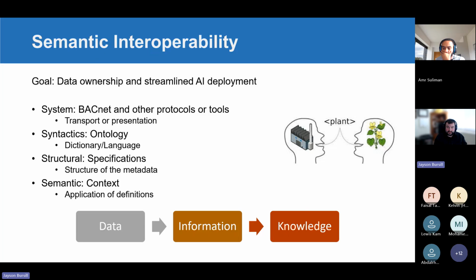Now, once you get there and you have all your data in one place, ontology becomes a thing - syntactics. So how do you know what things are? A lot of systems might have, for example, analog inputs or digital inputs, and the name of these in the software or firmware will be analog input 1, or AI 1. And from there, unless you have a separate document connected to something, you have no way of actually knowing that AI 1 - and this isn't artificial intelligence, this is analog input 1 - is actually a room temperature sensor.